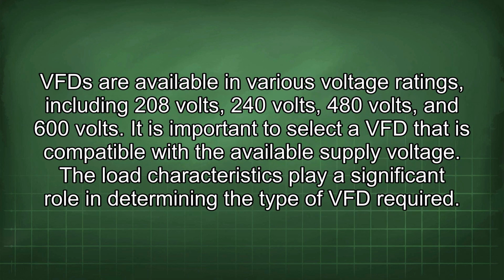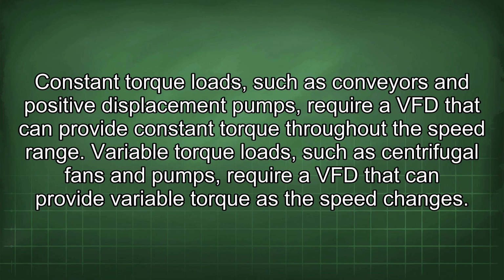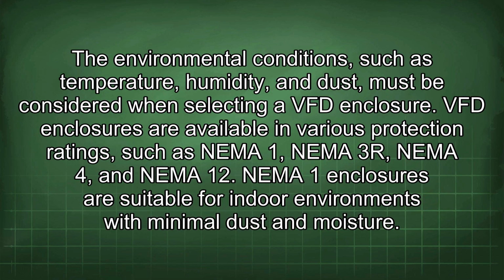VFDs are available in various voltage ratings, including 208 volts, 240 volts, 480 volts, and 600 volts. It is important to select a VFD that is compatible with the available supply voltage. The load characteristics play a significant role in determining the type of VFD required. Constant torque loads, such as conveyors and positive displacement pumps, require a VFD that can provide constant torque throughout the speed range. Variable torque loads, such as centrifugal fans and pumps, require a VFD that can provide variable torque as the speed changes. The environmental conditions, such as temperature, humidity, and dust, must be considered when selecting a VFD enclosure.